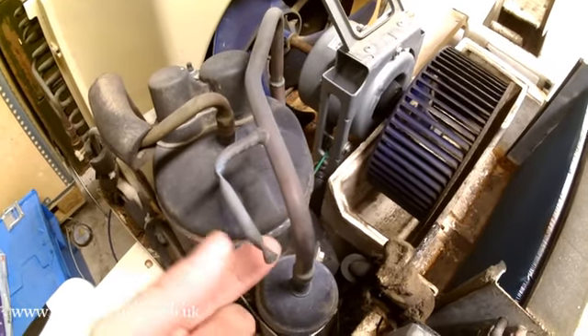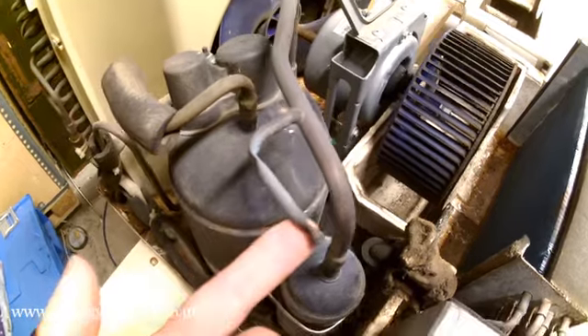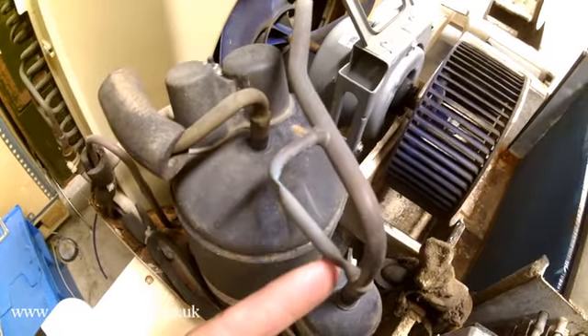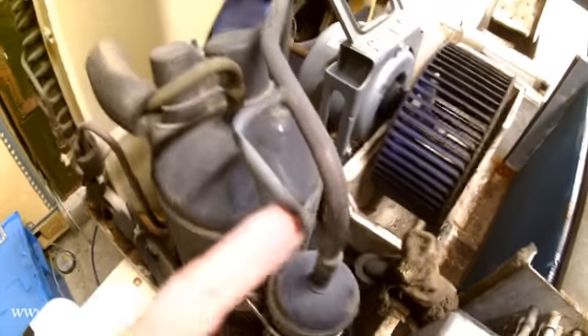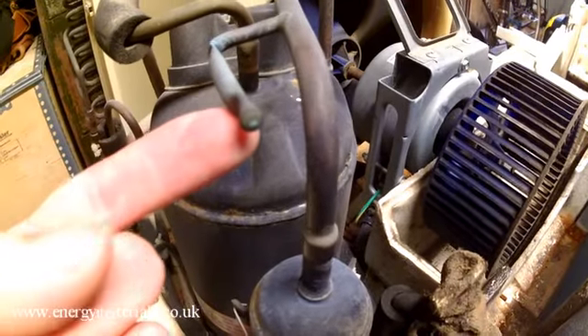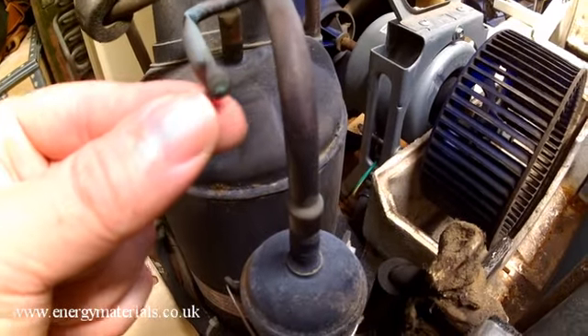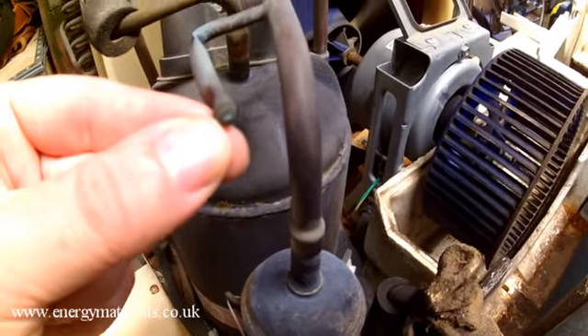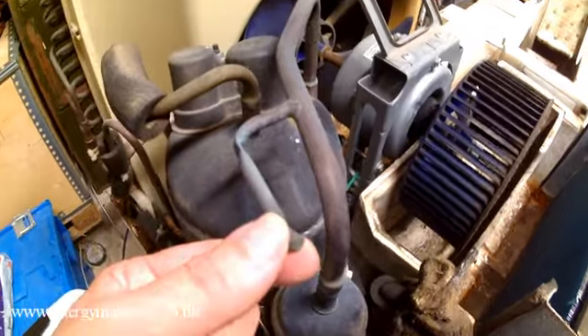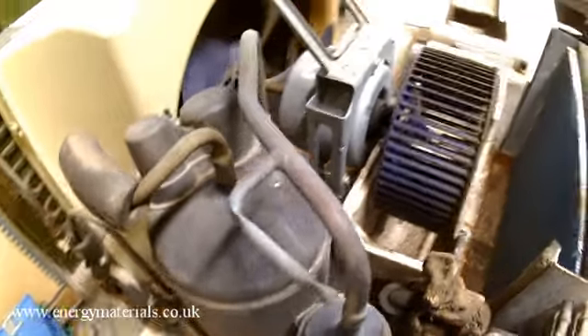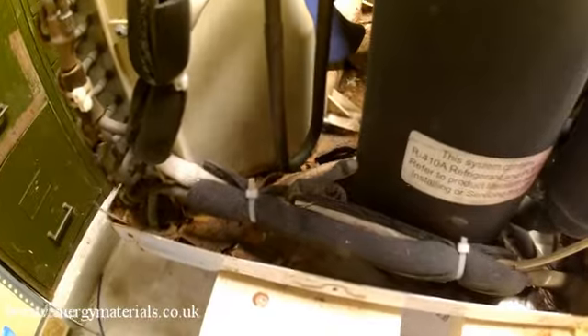After filling, this pipe is then crimped. It's crimped in two places. One crimp here, one crimp there to seal it. And as a final safety measure, there's a blob of solder or braze at the outside of this joint to hermetically seal the line or line set. And then there's another one on the high pressure side, again crimped in two places, and a blob of solder.